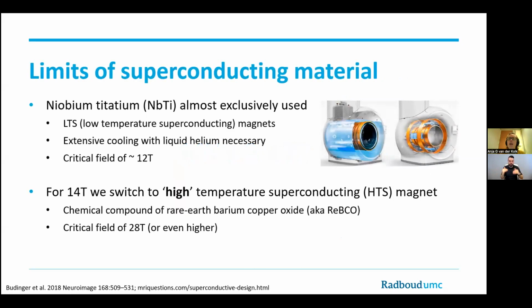Because normally in MRI scanners, we use niobium titanium. It's almost exclusively used. It's a low temperature superconductor. That means that it needs extensive cooling with liquid helium. This is the inside of an MRI scanner. You can see the liquid helium. This is another one. I don't even know the vendor. But anyway, you can see that the liquid helium pockets are a little bit smaller, but essentially you need extensive cooling. And it has a critical field of up to 12 Tesla, which means that getting a field strength of 12 Tesla is relatively difficult without problems.